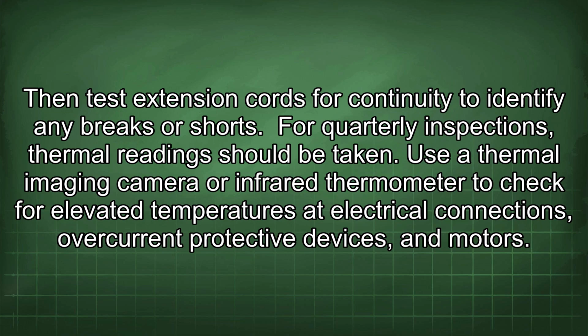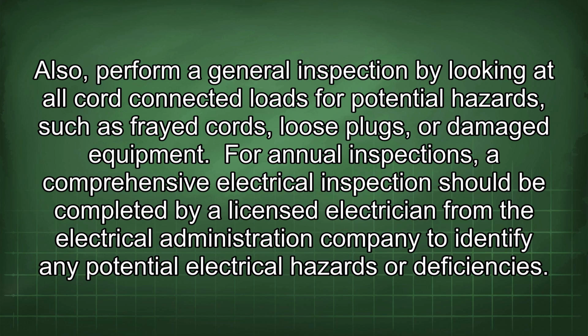For quarterly inspections, thermal readings should be taken. Use a thermal imaging camera or infrared thermometer to check for elevated temperatures at electrical connections, overcurrent protective devices, and motors. Also, perform a general inspection by looking at all cord-connected loads for potential hazards such as frayed cords, loose plugs, or damaged equipment. For annual inspections, a comprehensive electrical inspection should be completed by a licensed electrician from the Electrical Administration Company to identify any potential electrical hazards or deficiencies.